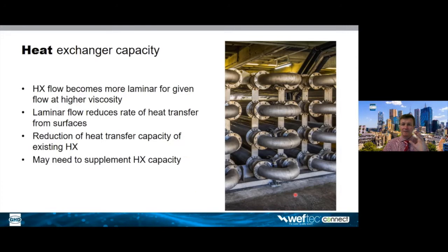And that was the case on one of the projects that I was involved in several years ago, where a very large additional heat exchanger was required and was in fact installed on the raw sludge stream as opposed to on a recirculation stream from the digester itself.